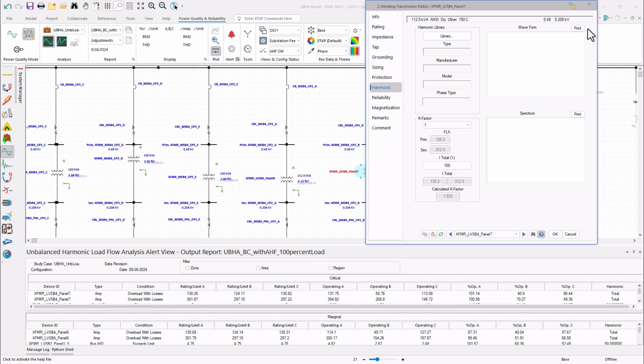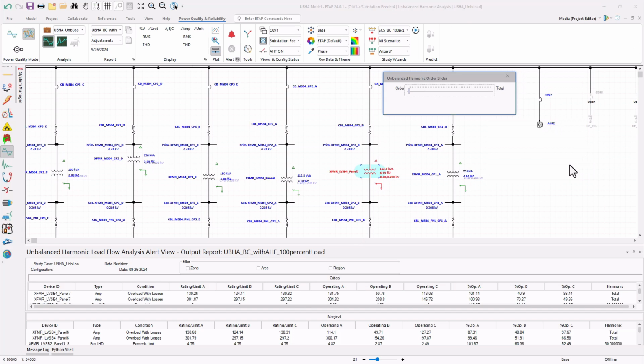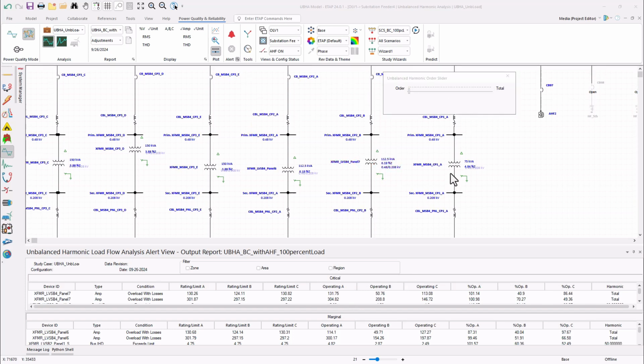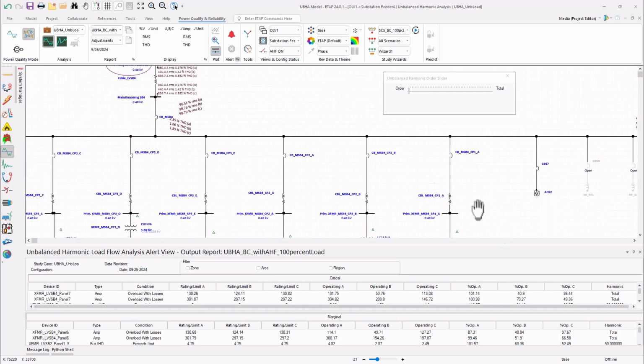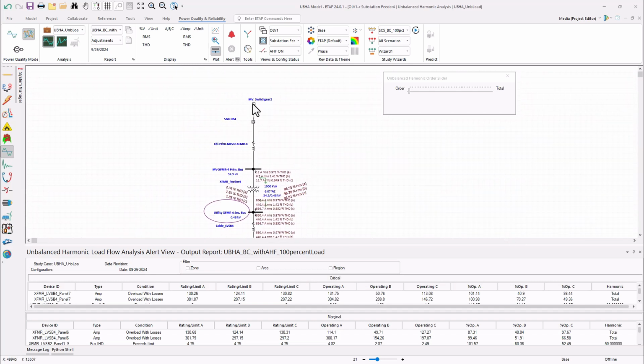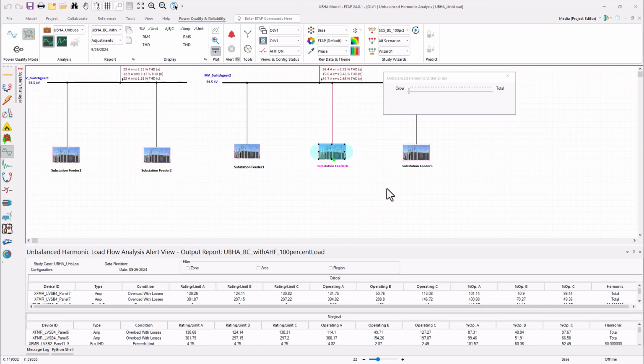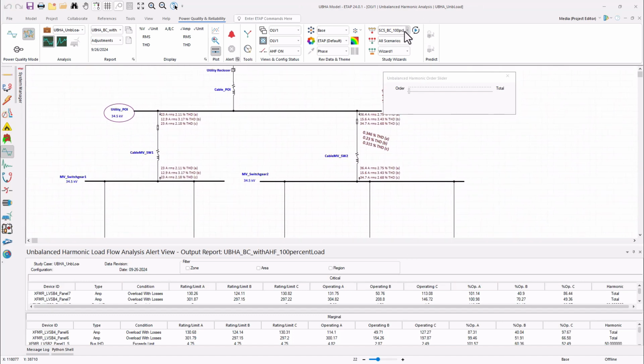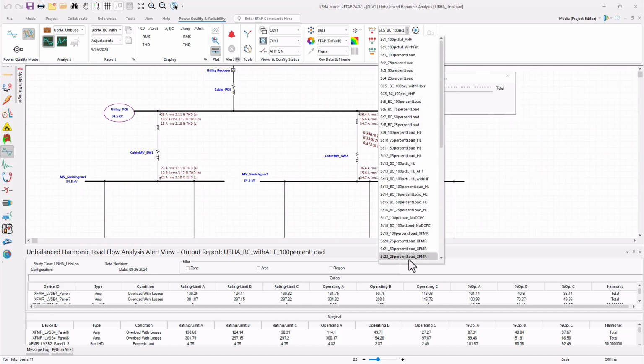So some transformers were found to have continuous overload due to the effect of harmonic distortion. So alerts, as we're seeing, are generated based on the derating factor calculated from the harmonic content in the current injections. So to sum it all up about this case, all the EV charging sites that were considered for analysis were modeled in ETAP using ETAP digital twins. And for all those sites, several scenarios were created considering all possible conditions and configurations to perform the analysis.